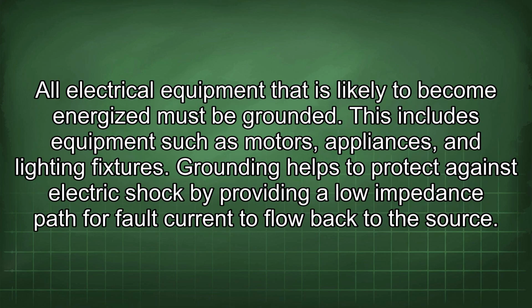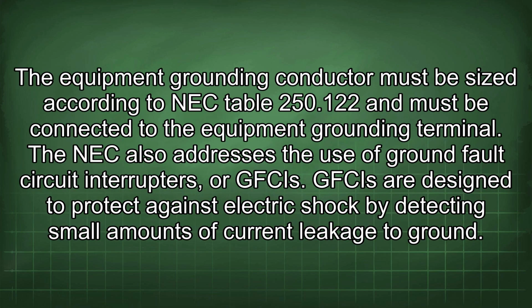The NEC also addresses the grounding of equipment. All electrical equipment that is likely to become energized must be grounded. This includes equipment such as motors, appliances, and lighting fixtures. Grounding helps to protect against electric shock by providing a low impedance path for fault current to flow back to the source. The equipment grounding conductor must be sized according to NEC Table 250.122 and must be connected to the equipment grounding terminal.